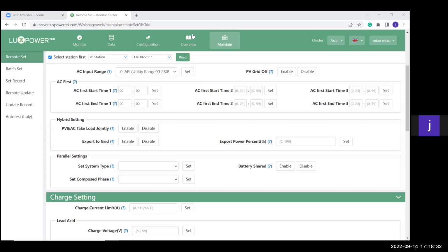Your PV power will always be prioritized to your batteries first if PV AC jointly is not active. As soon as PV AC jointly is active, the inverter will prioritize the panels to the loads first.